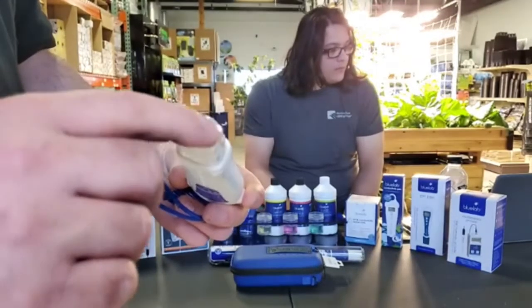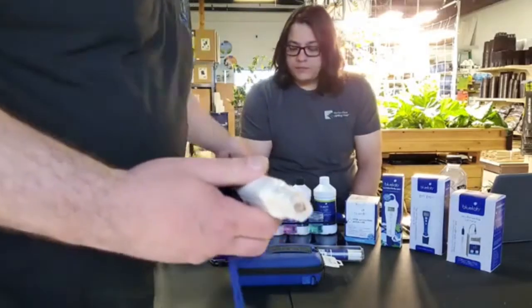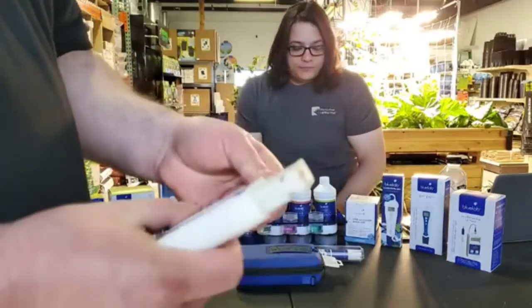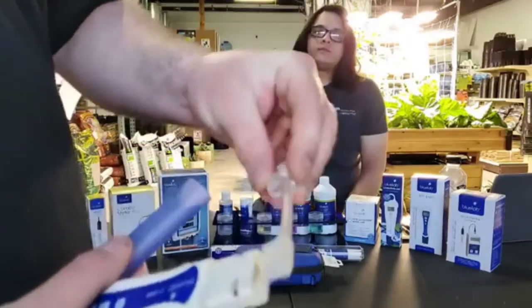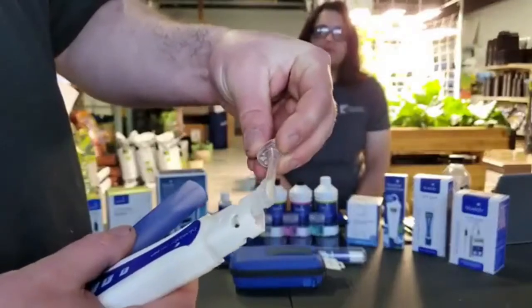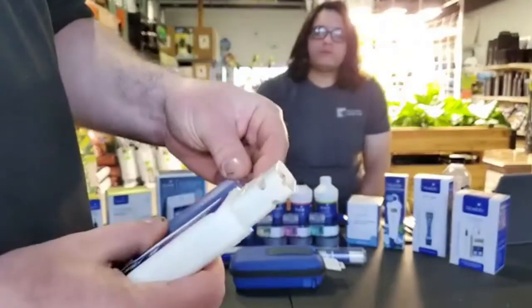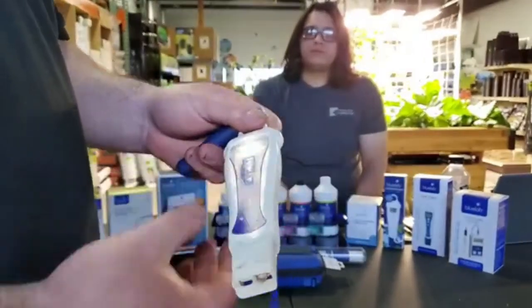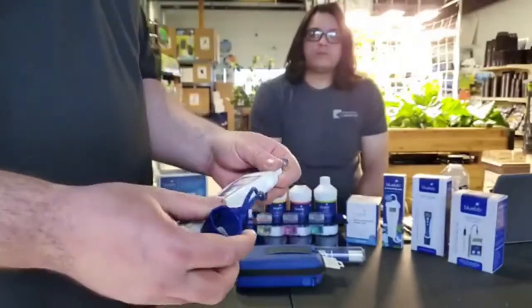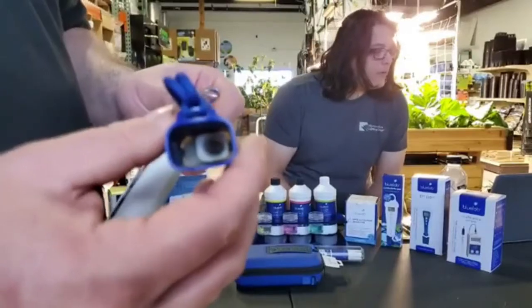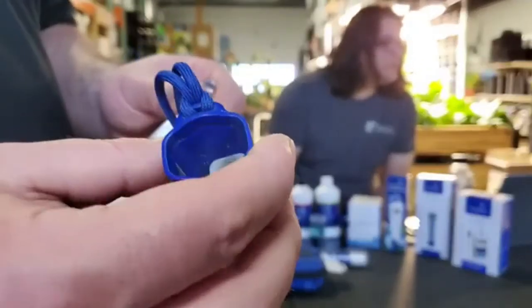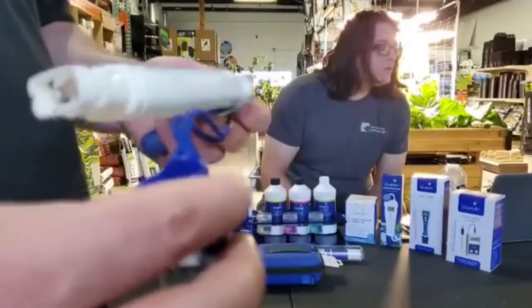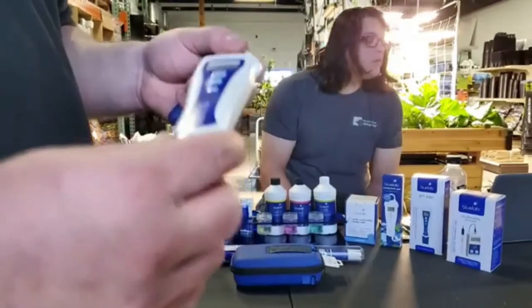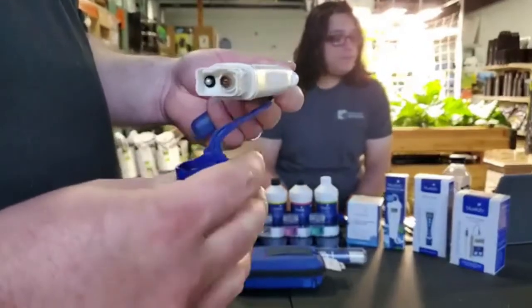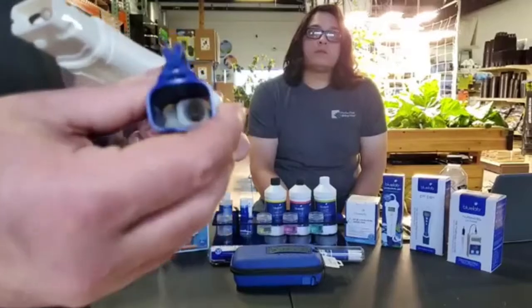And so the bulb is really the important part. You want to keep this all clean, and that's where the toothbrush comes in the care kit. You take a little bit of the soap, put it onto the toothbrush, and then simply scrub the cleaner around, and it'll dissolve any collected mineral salts or anything like that that's on your probe, and then you just rinse it off, and you're good and clean. Another important thing to know about these pH meters is these caps. If you can see inside that cap, there's a little silicone ring and a foam sponge in there, and that's actually to house that bulb when you have the cap on. You always want to keep the cap on this pen when it's not in use, and you always want to keep that little sponge wet.